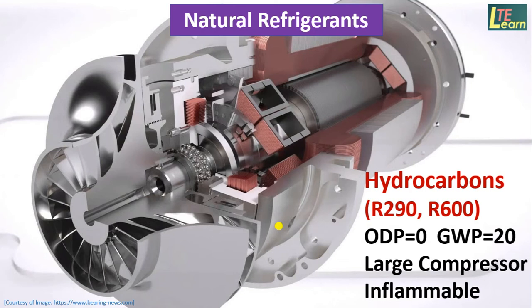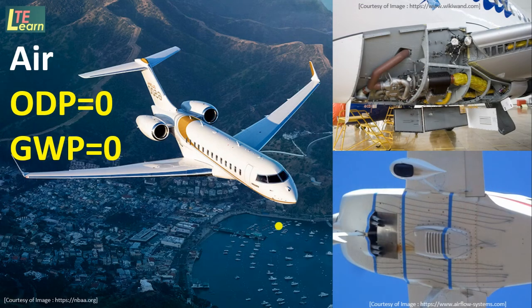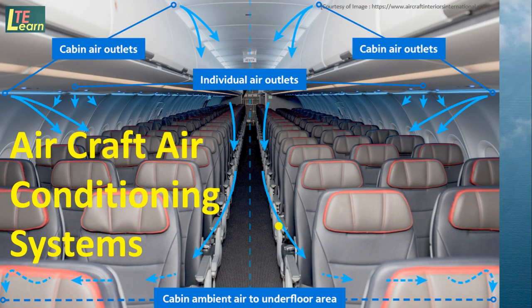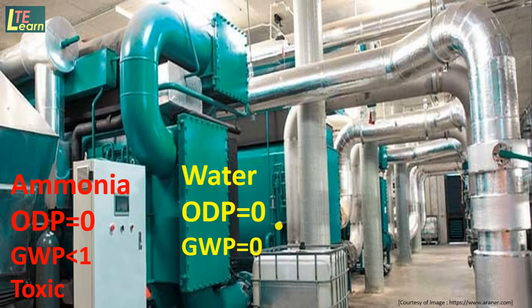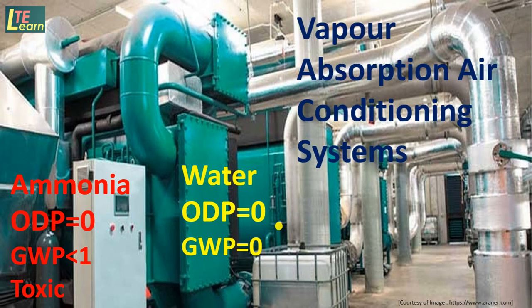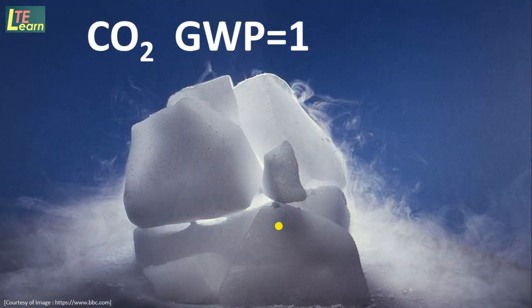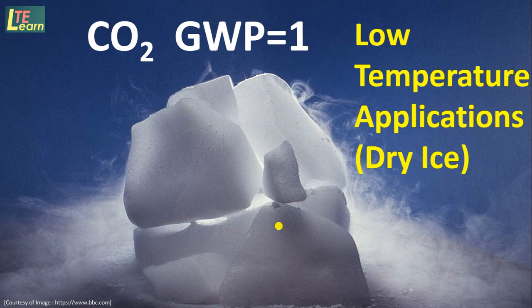Natural refrigerants such as hydrocarbons — propane and butane — are used in large compressors, but they are inflammable in nature. Air, because of its ODP and GWP of zero and its light weight, is used in aircraft air conditioning systems. Ammonia is used as a primary refrigerant and water as a secondary refrigerant in vapor absorption air conditioning systems. Carbon dioxide is used in low temperature applications as dry ice, but it has a limitation of critical temperature at 31 degrees Celsius.